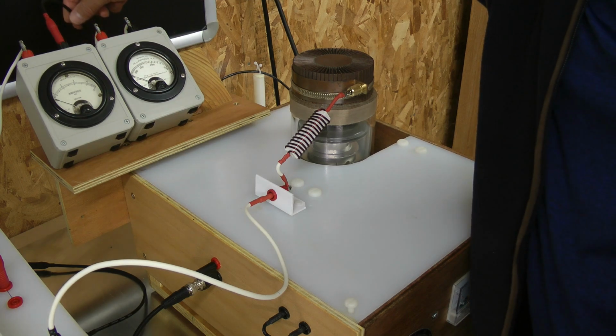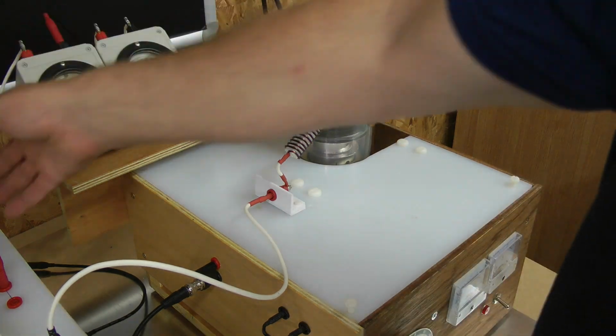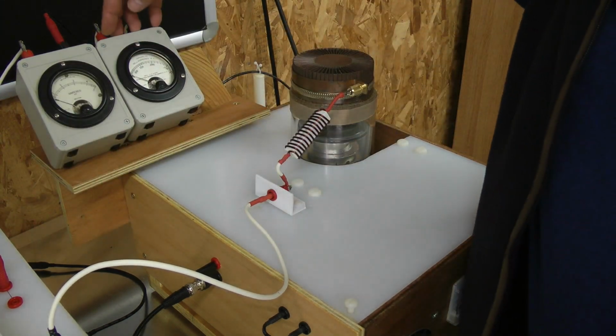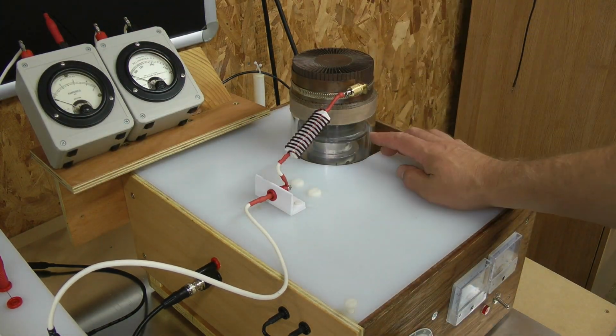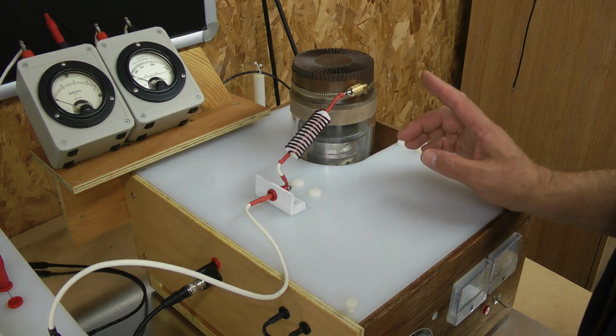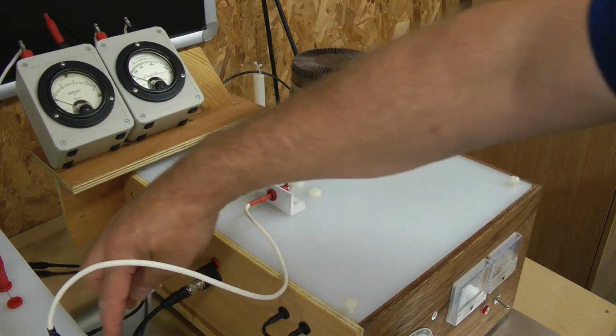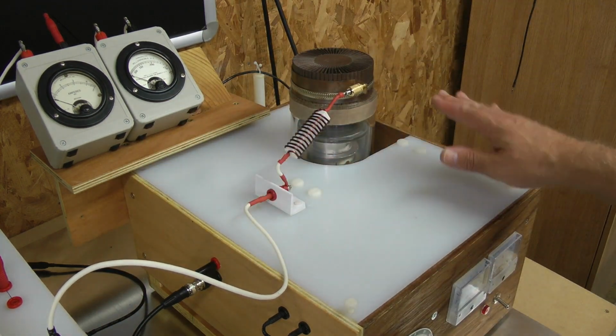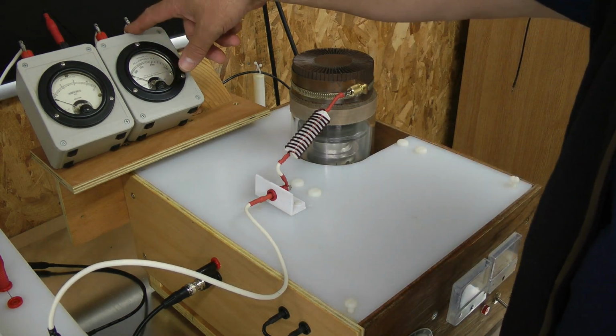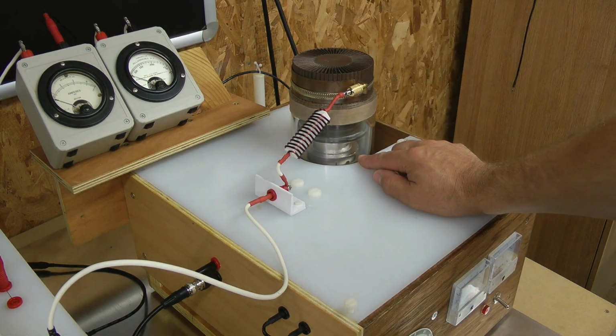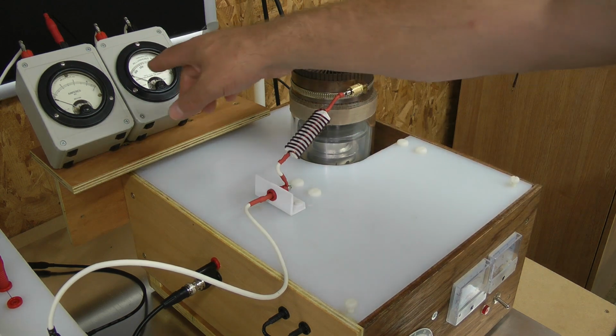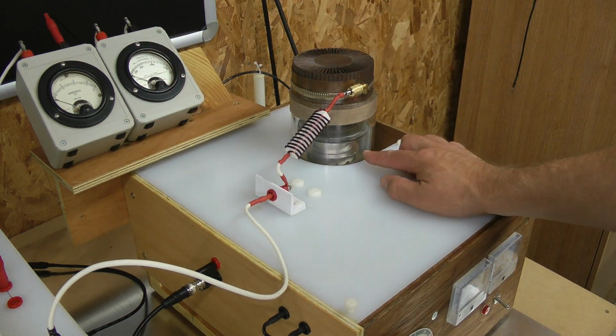This is the incoming high voltage, HT. This basically is one side of the primary, and this is the grid current directly going to the grid of the tube. So we've got a grid leak bias circuit for the oscillator, and then after that it comes via this meter and then straight onto the grid of the tube. So this is the last step before the grid connection to the tube. So you can see the grid current and you can see the plate current here.